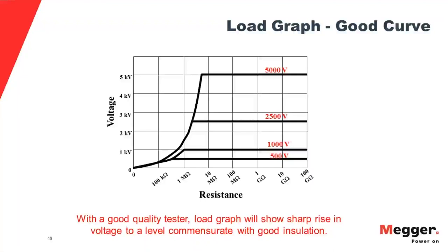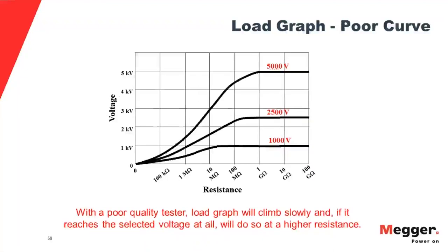What you don't want to get is something like this, where it gets there eventually, but over the low end of the resistance scale, and that's where you have to make your most critical determinations, when the insulation is getting down towards its low end, but is still good, is still operative, but you've got to make some decisions. When do I want to test this again, or when do I want to take it out of service and recondition it? And if you have a poorly designed tester with a poor load graph, that is not going to give you valid information. So look for your load graph.